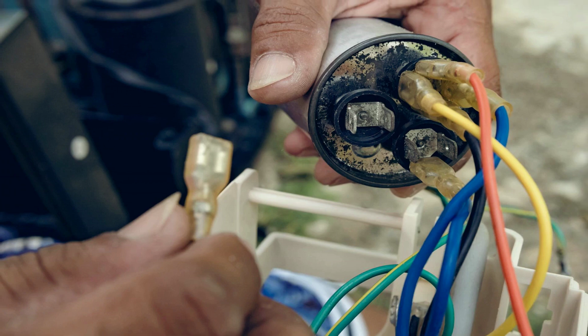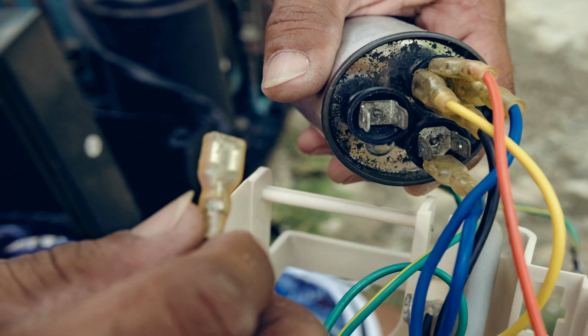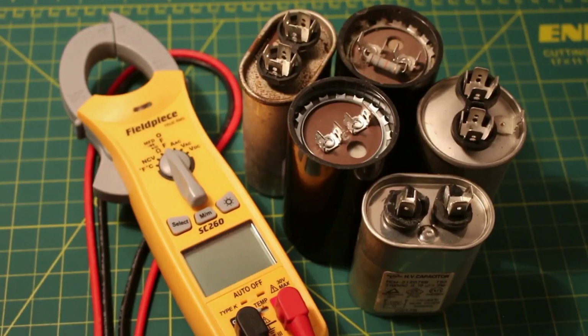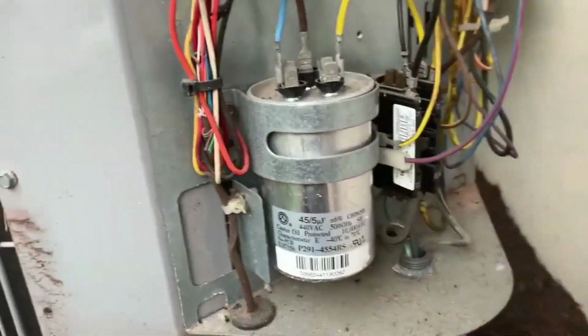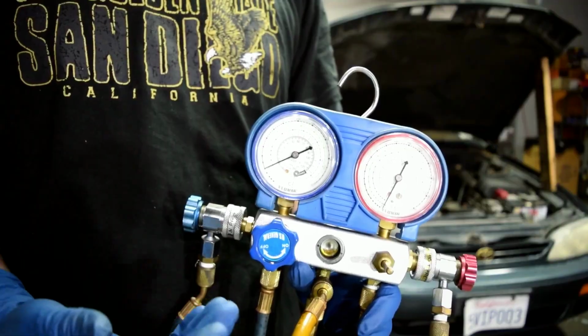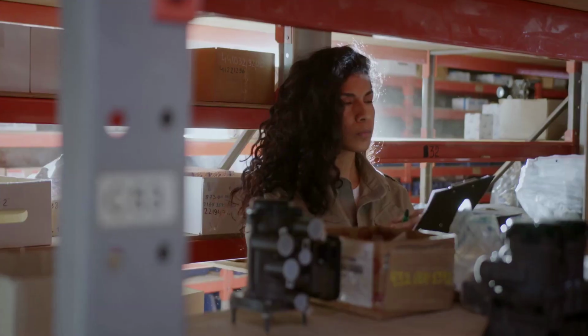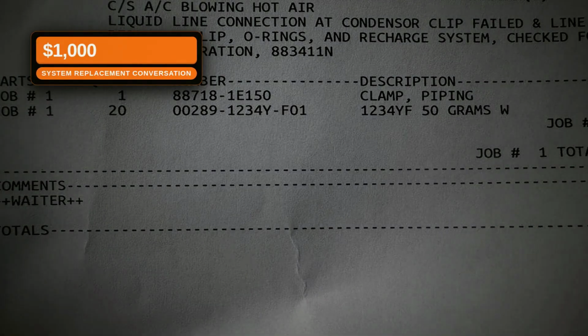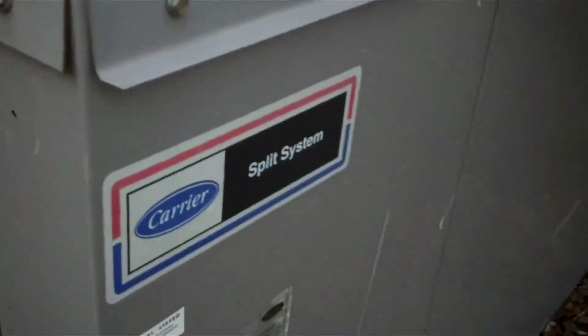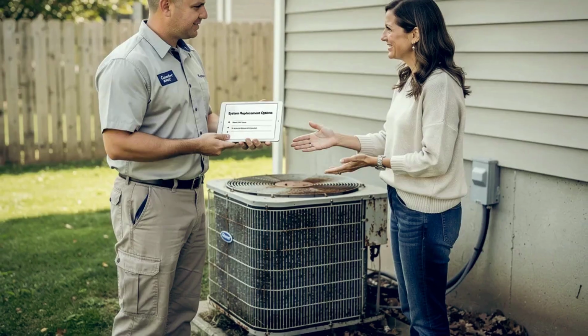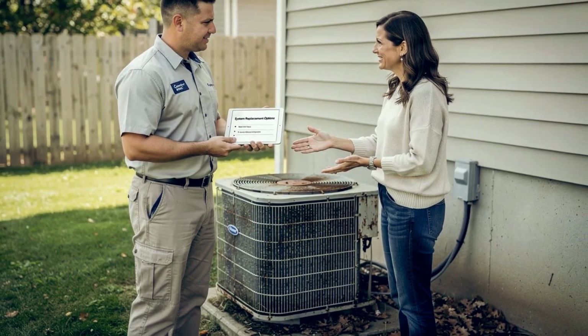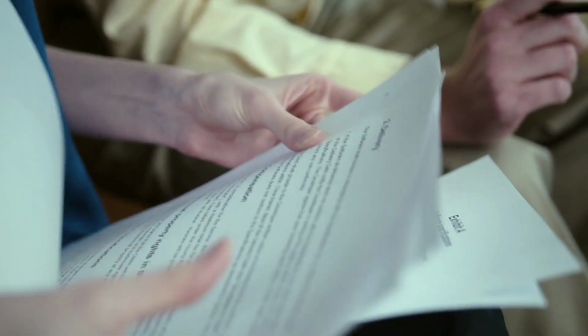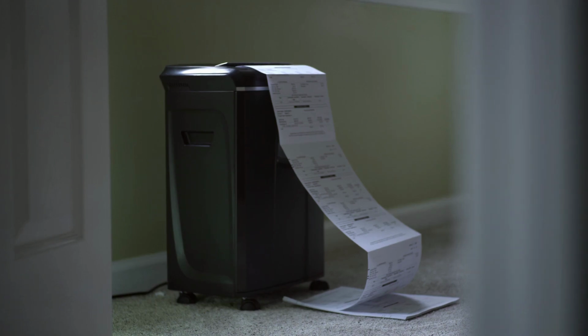Technicians are often incentivized to escalate. A failed capacitor is a legitimate entry point for a broader system evaluation. That evaluation can reveal or manufacture concerns about refrigerant levels, compressor health, or system age. A $400 capacitor call has a documented pattern of becoming a $6,000 system replacement conversation. That escalation is not always dishonest, but it is structurally encouraged. The tech who closes a replacement sale generates significantly more revenue than the tech who swaps a part and leaves.